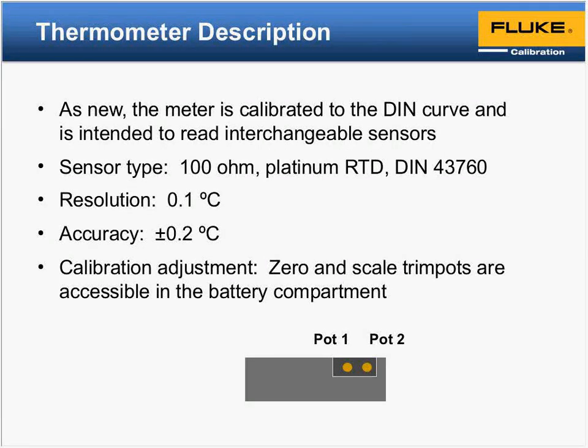Usually the readout pieces are calibrated to a DIN curve or intended to be used with specific TCs. When I say a DIN curve, that's referring to an RTD, usually the IEC DIN class A or B type. So again, typically that's just a defined 100 ohm platinum RTD with either class A or class B specification. And that's what we're looking at here. Our readout has a resolution of 0.1 degrees C and it's supposed to be accurate to 0.2 degrees C.